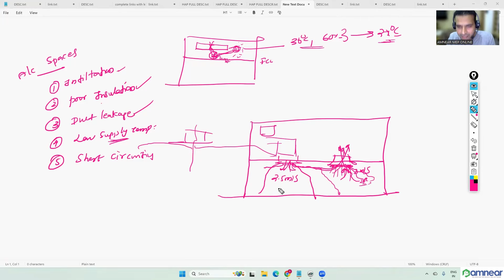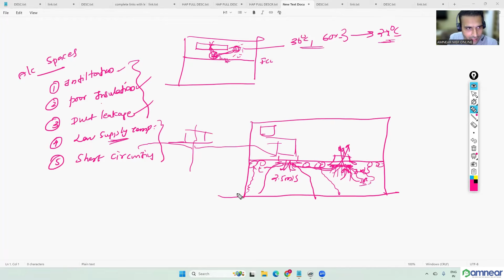So if the air distribution is not proper, if the throw selection is not proper, sometimes cold pockets will get generated on surfaces inside the spaces. In that scenario also, when hot air is having contact with those cold regions, condensation can come. But low supply temperature and short circuiting are negligible reasons only. The major reasons of condensation within the air conditioned spaces are these first three only: infiltration, poor insulation, and duct leakage. Low supply temperature also can cause it, because if condensation is happening on the surface of air terminals, the major reason is low supply temperature only. Okay, these are the reasons of condensation within air conditioned spaces.